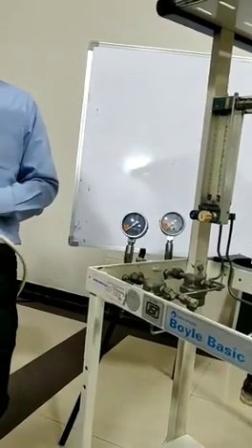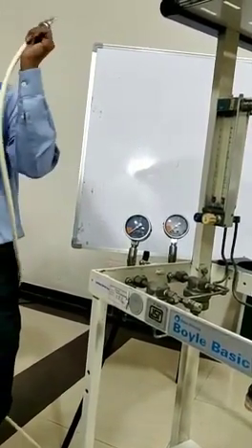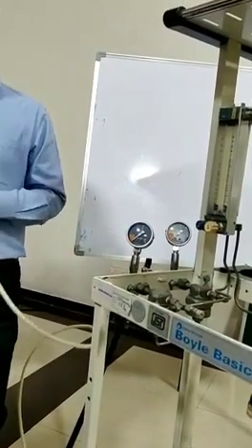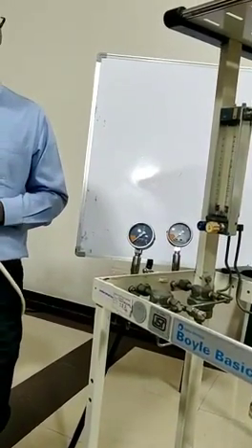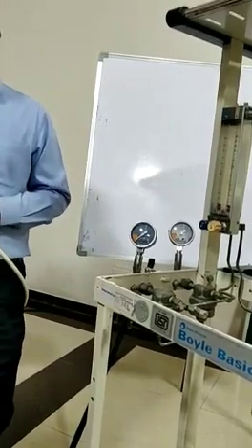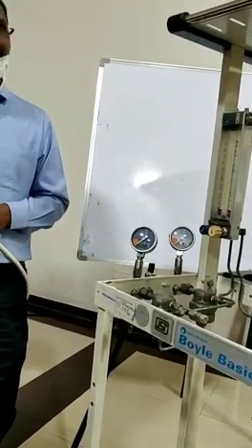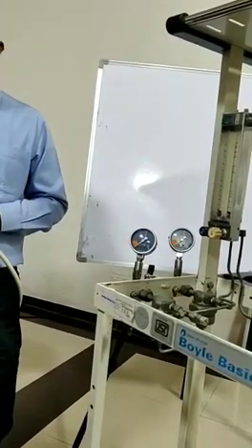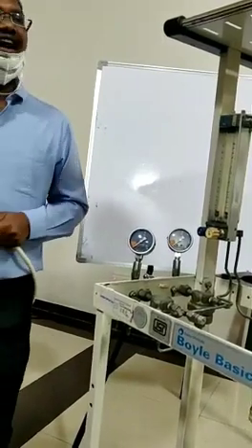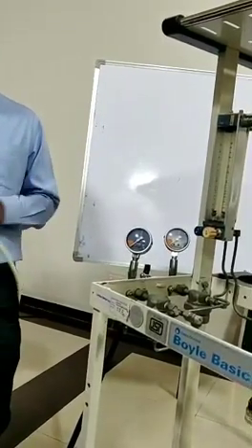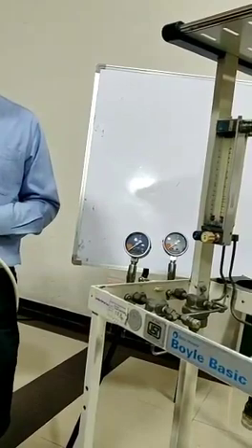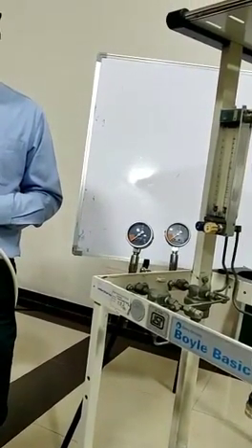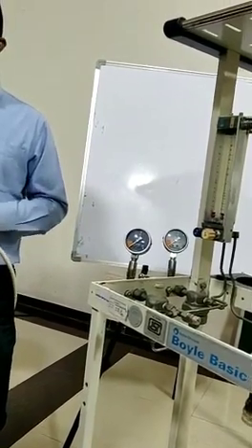Then it comes through multiple copper tubes, which are color coded specifically, white for oxygen and French blue for nitrous oxide. Fine. Why is it made up of copper? It is bacteriostatic. It resists corrosion, and it is bacteriostatic. What is the diameter of the copper tube in the pipeline? Okay, the diameter of the copper tube pipeline.